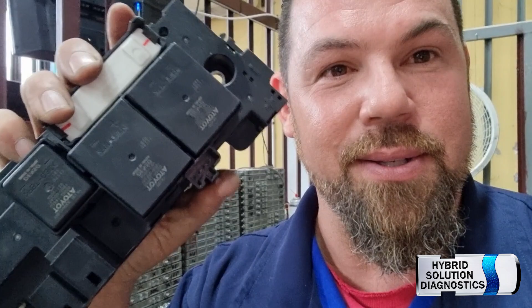Be very honest, I've never seen a Denso contactor in bad condition. Those are sealed contactors — even vacuum inside the porcelain, where it makes the contact, it's inside a porcelain chamber, completely sealed and vacuum. So you take it apart and open it and it looks as good as new. It never gets overheated, nothing. But this one does — the connection between this pin and that one inside the relay burns out and melts. This is the reason why.